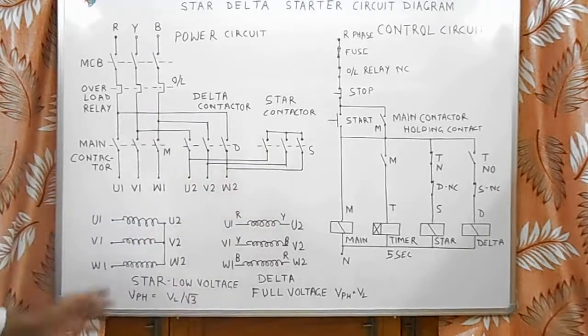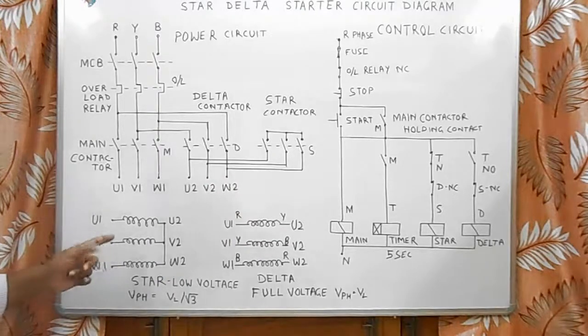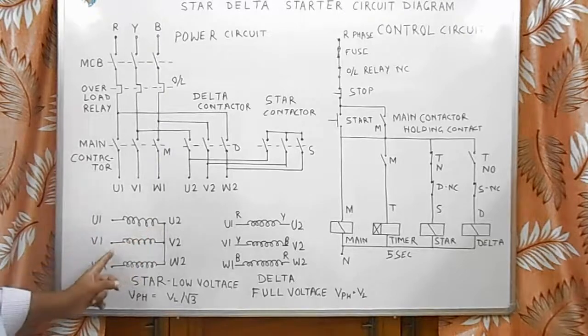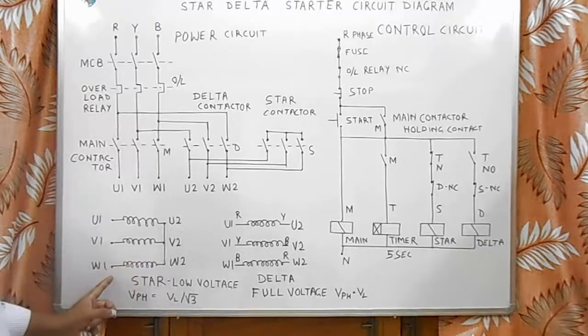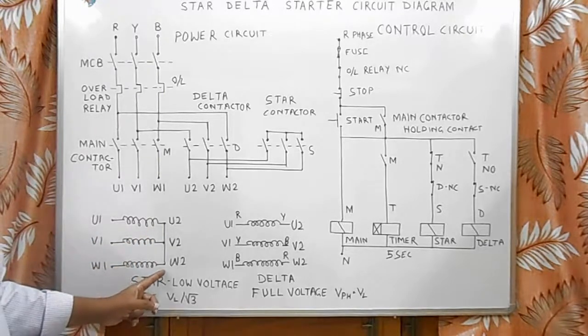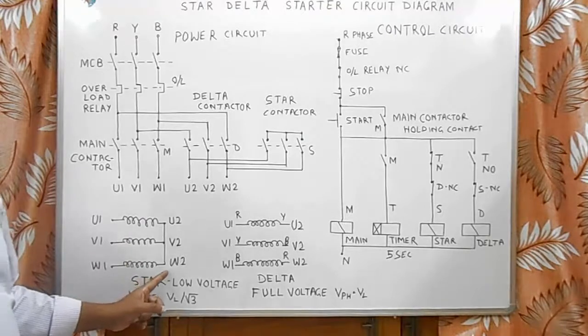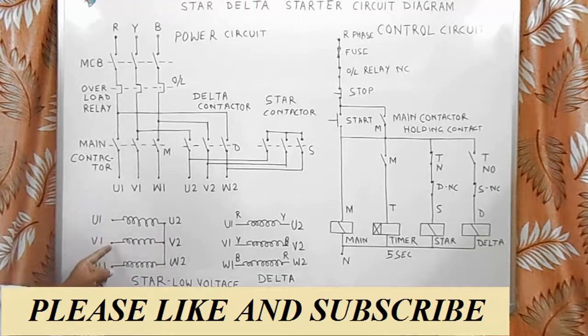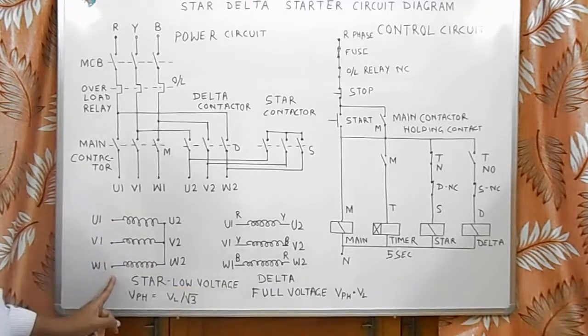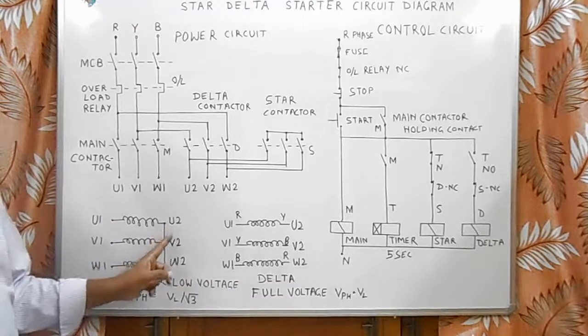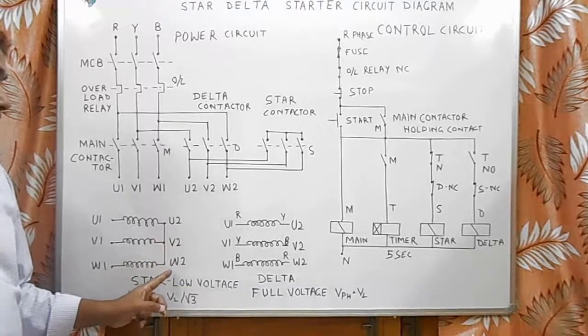When any three-phase motor has three windings, these windings are named as U1-U2, V1-V2, W1-W2. When we want to start at low voltage, we connect these windings into star connection. U1, V1, and W1 are given supply and U2, V2, W2 are short-circuited.